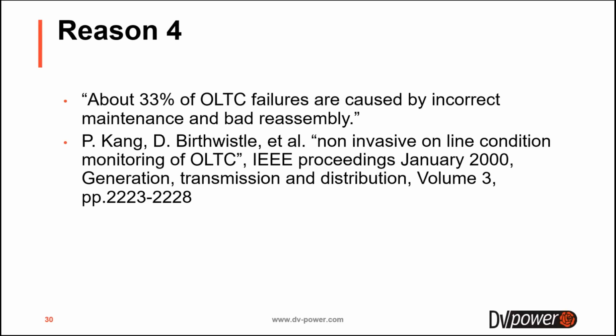And last but not the least, around 1/3 of failures are caused by incorrect maintenance and bad reassembly. So even if you do maintenance, if you do the reparation, depending on how experienced the people doing it are or not, that can even cause some problems. And it's always good to test, to check the OLTC even after the maintenance and after the reparation. And DVtest is just a very nice tool for checking the OLTC after the maintenance, just to make sure that everything is repaired correctly, everything is reassembled correctly.